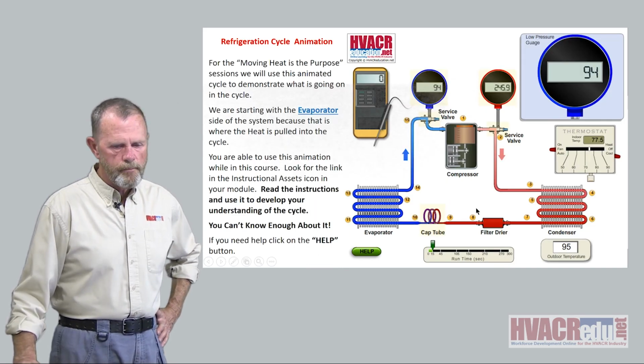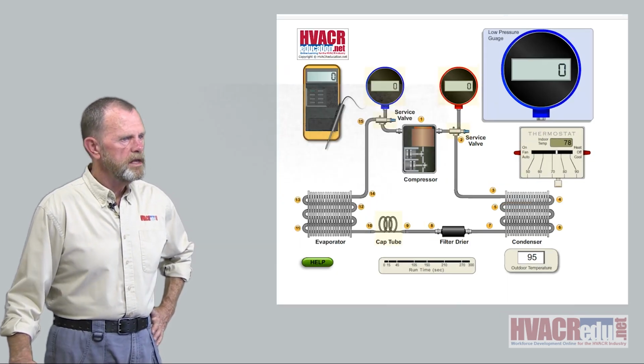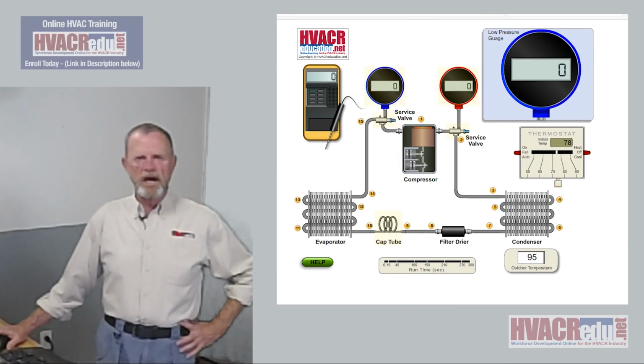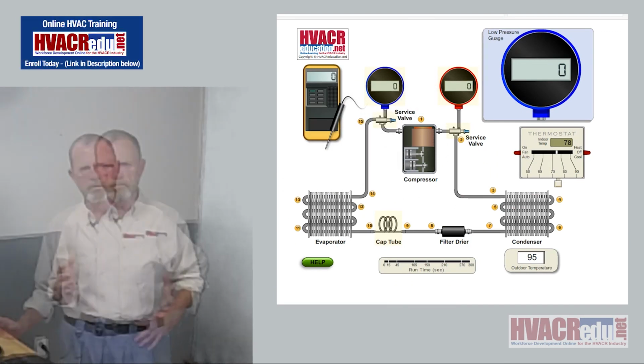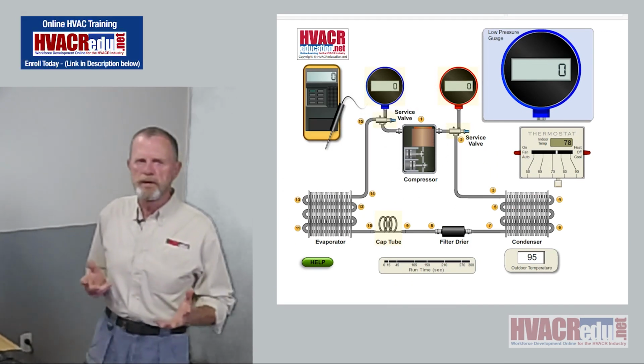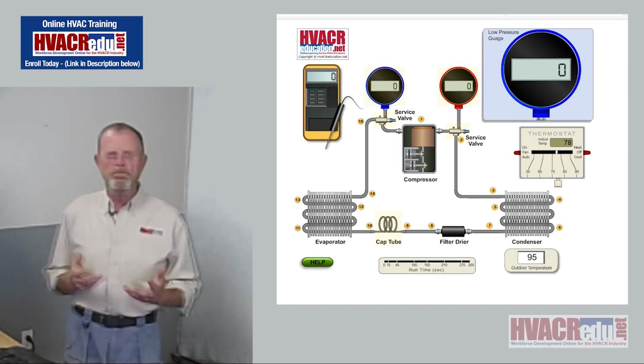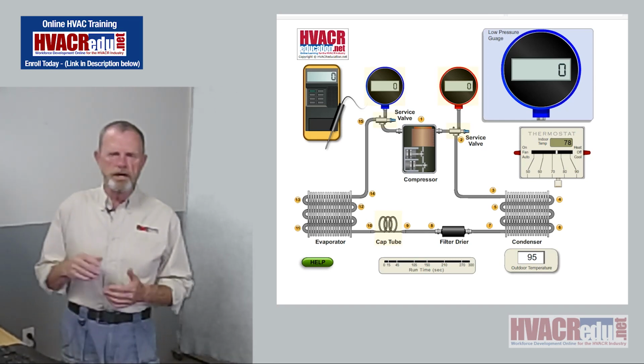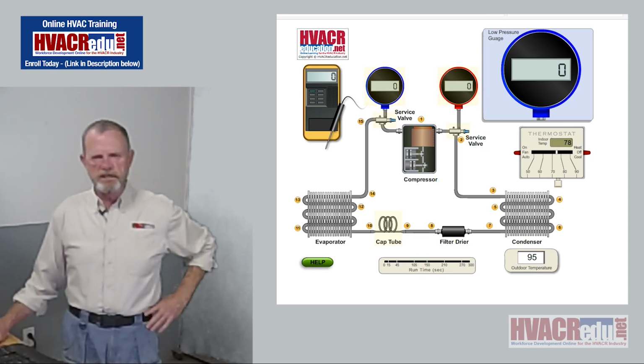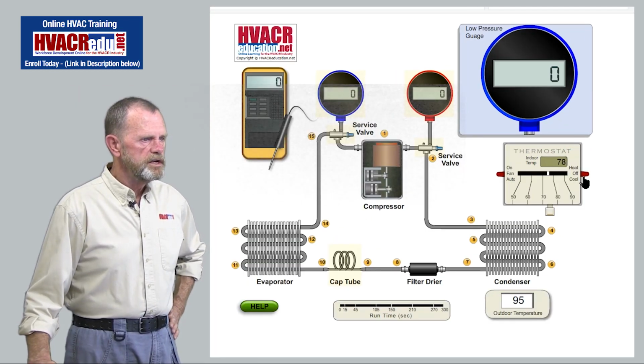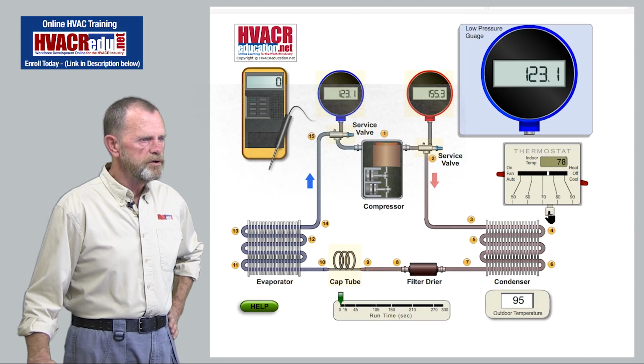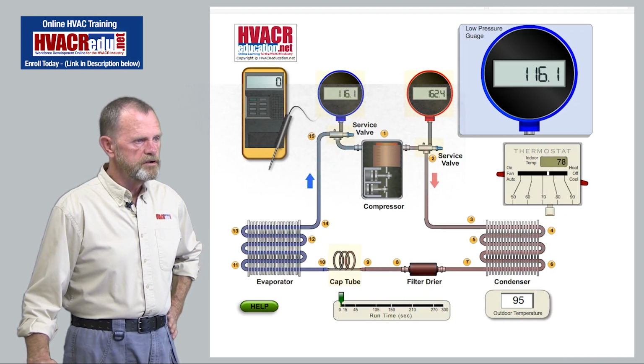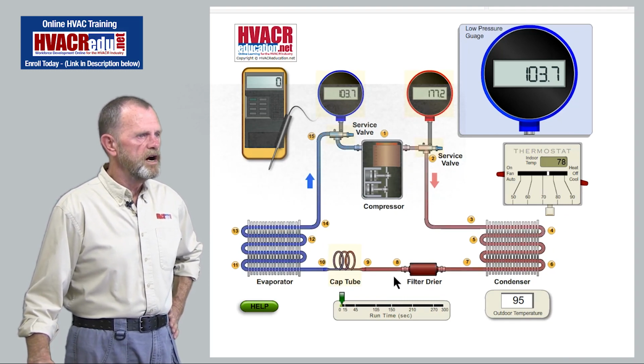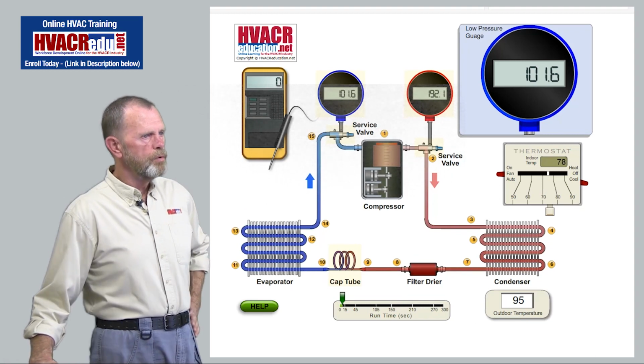So with that, I just want to put this up real quick. In our course, you have access to this animation, and the rest of this presentation is based on this animation. If you're in the course, you'll have access to it. You'll have to open it up, and then you'll have to energize it. You energize it by turning the switch to cool, just like you would in real life. You've got to turn the thermostat down. You've got to select it to cool, and then turn the temperature down to 75. And that starts the system going, all right?